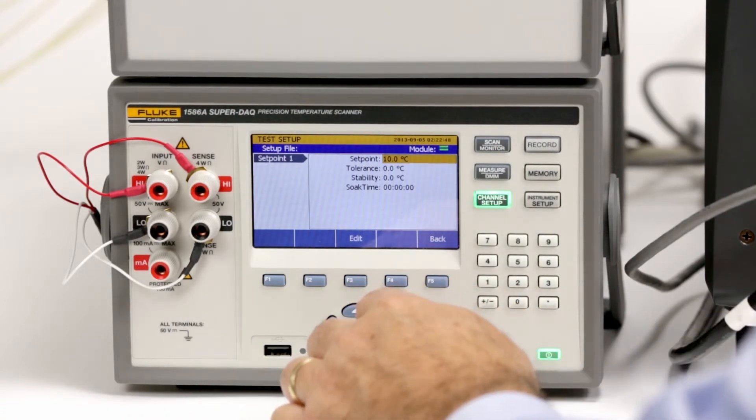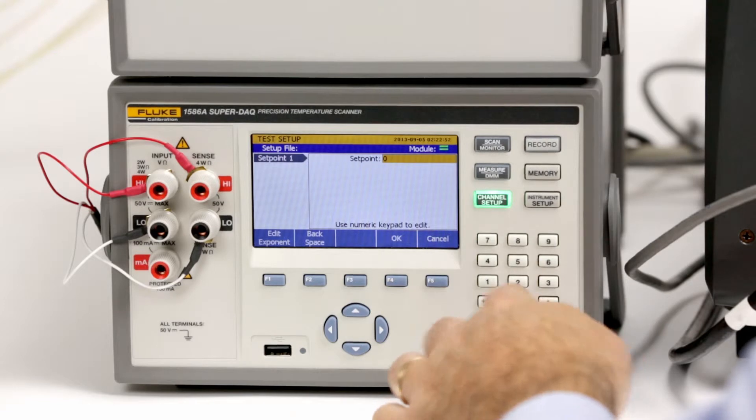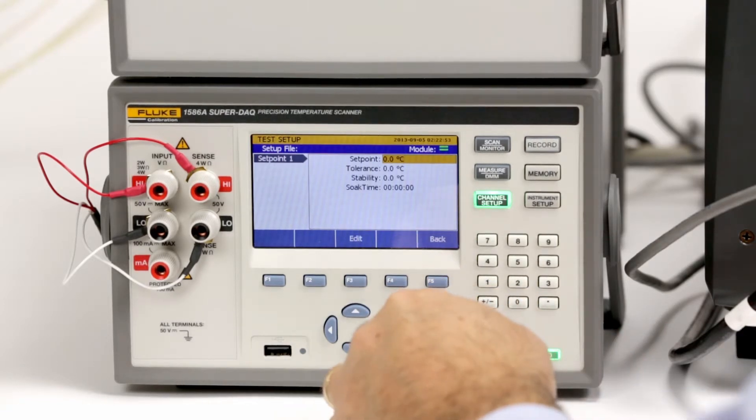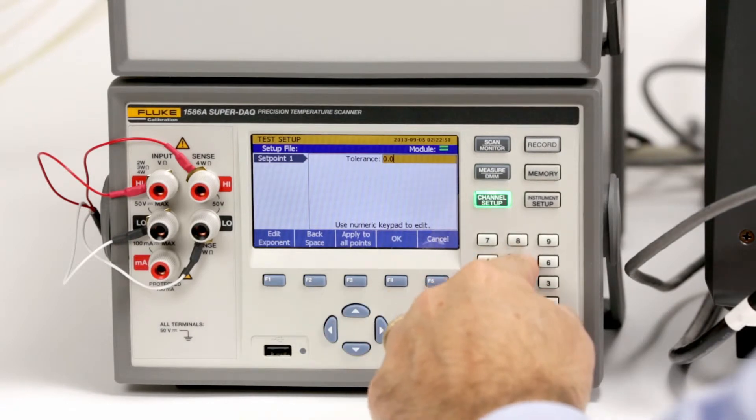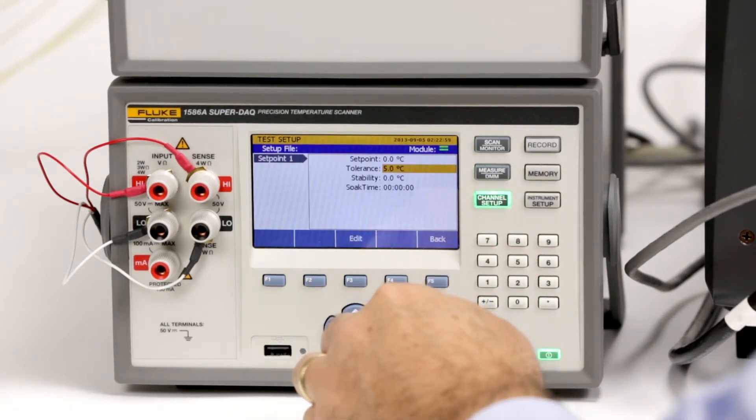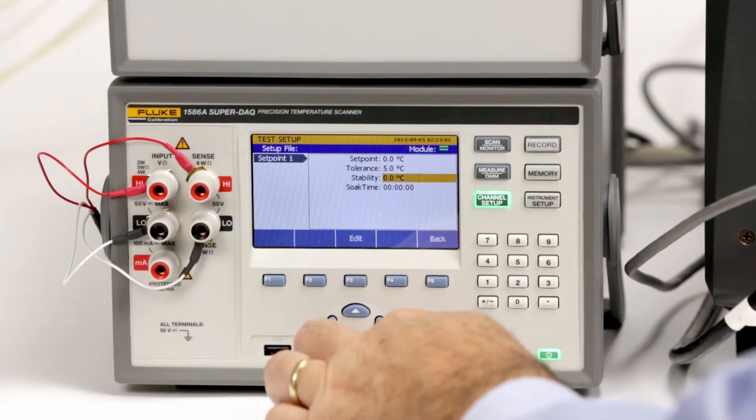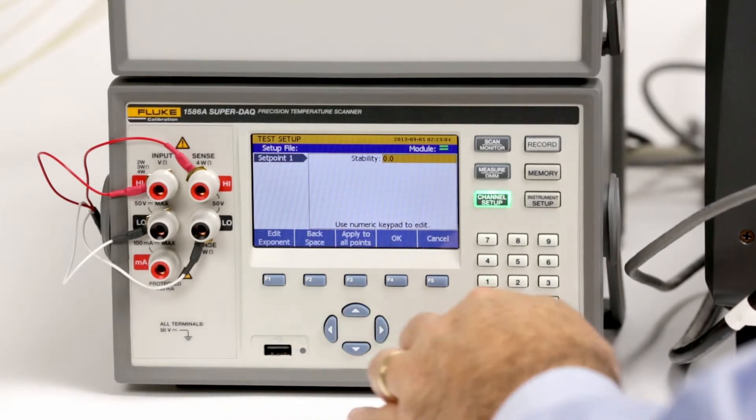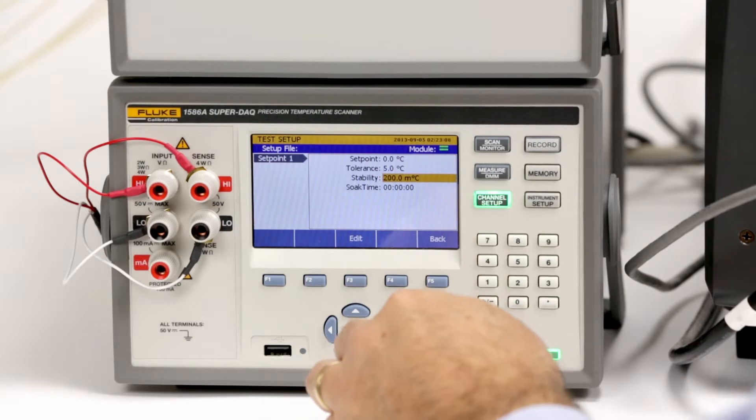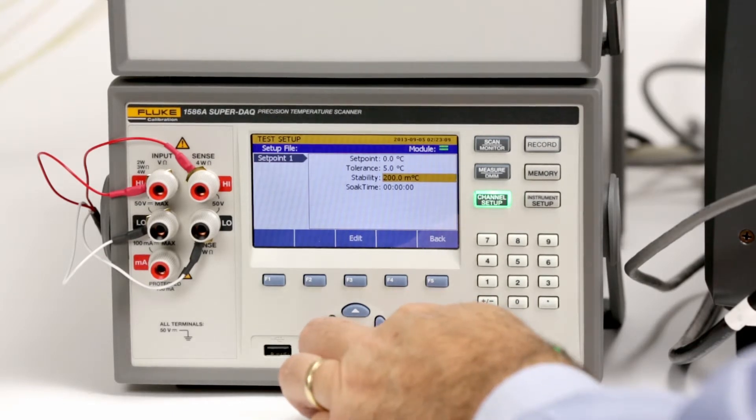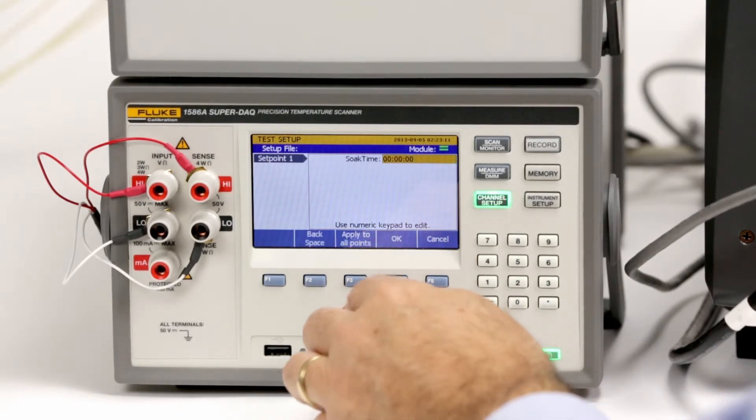Select set point 1 and enter set point temperature 0 degrees C, tolerance 5 degrees C, stability 0.2 degrees C, and soak time 5 minutes.